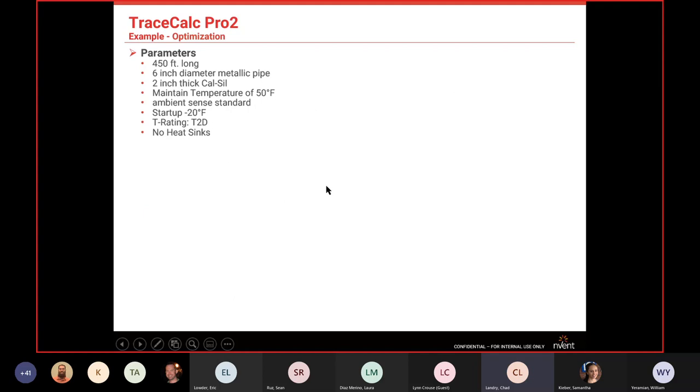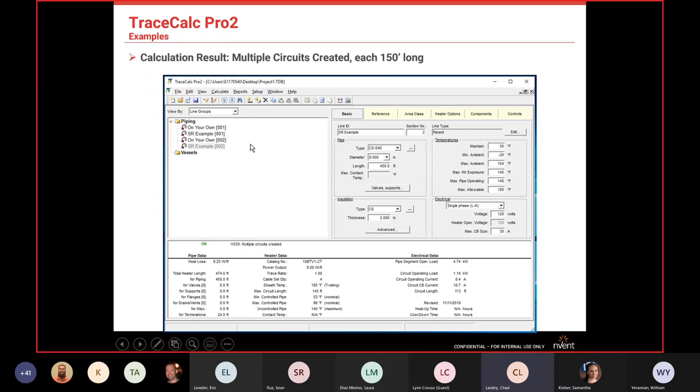Here's a worked example using customer-provided information: 450-foot, 6-inch diameter metallic pipe; plant spec calls for 2-inch calcium silicate insulation; maintain 50°F; ambient-sensed freeze protection circuit; startup at minus 20°F; T2 area rating; no heat sinks.